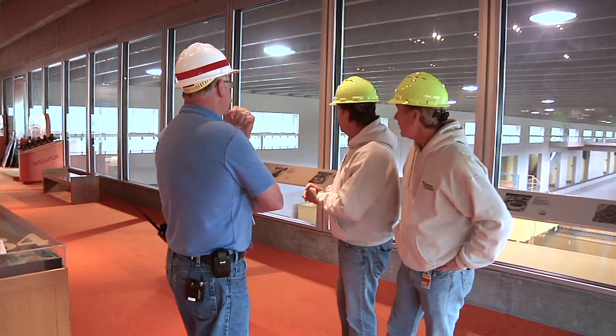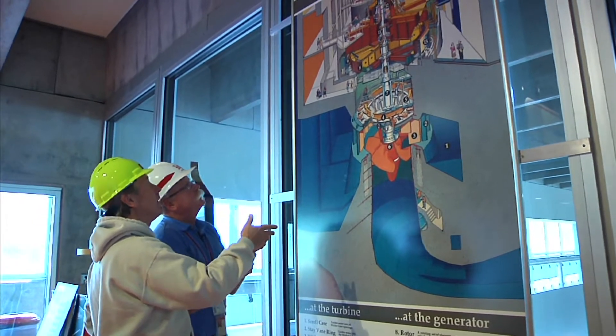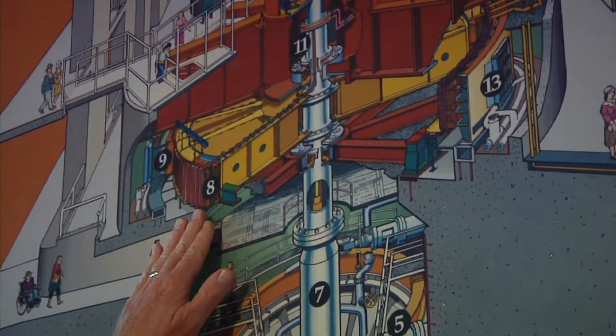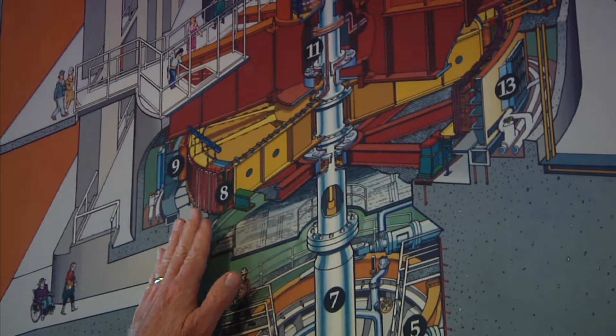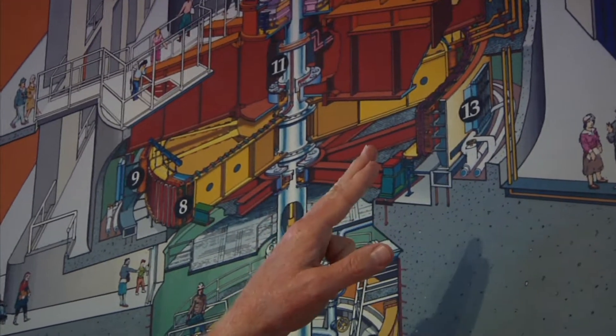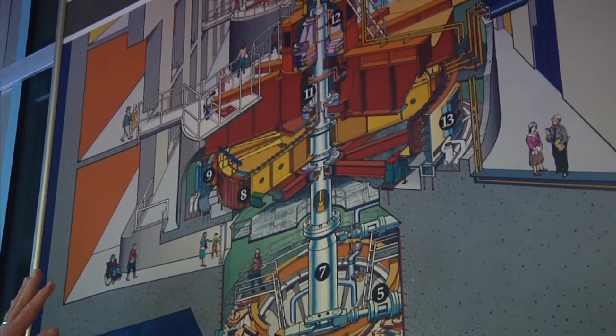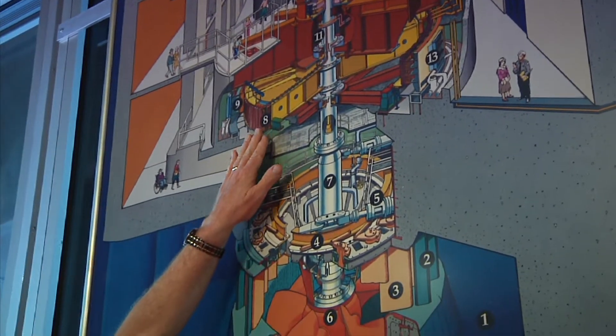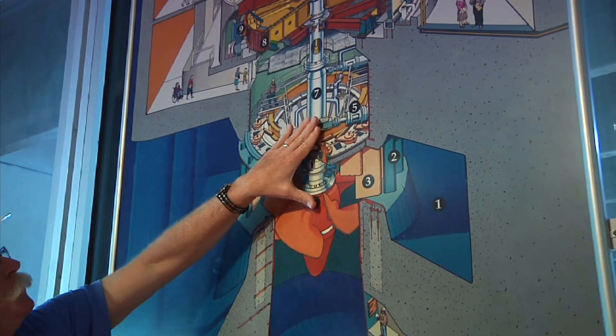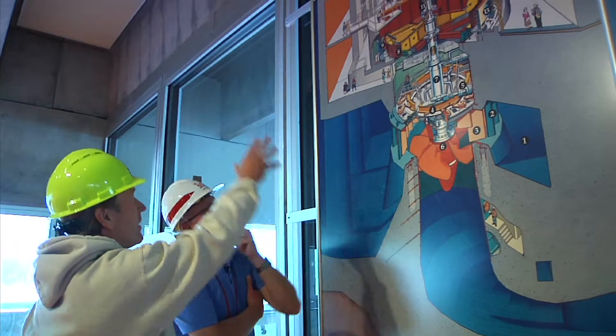Looking at the inside of the dam and a cutaway of a turbine: the rotor, identified as item number eight, is a rotating electromagnet used to generate electricity into a stator field, which goes out through electrical conductors to the system. The large bracket above is an upper bearing bracket, or thrust bearing bracket, and it supports the weight of the rotor — which weighs 430 tons — plus the turbine. The turbine weighs about 200-plus tons, so we have about 600 tons of rotating equipment in every large turbine.